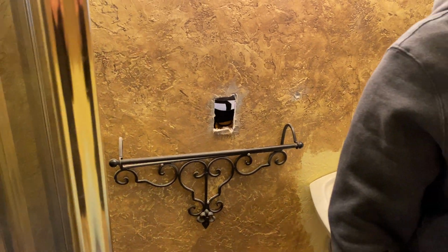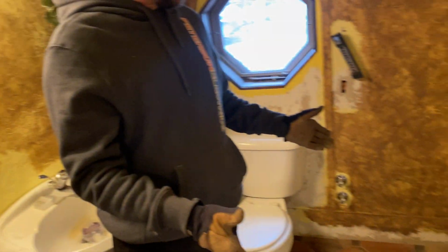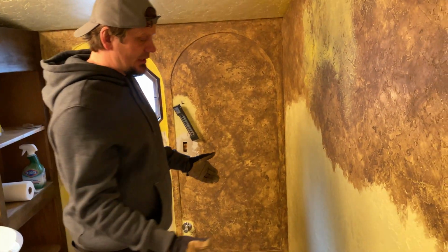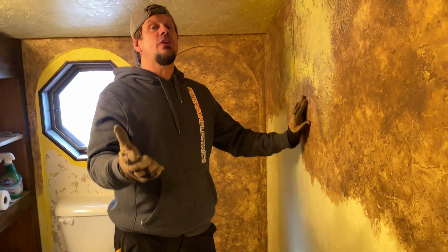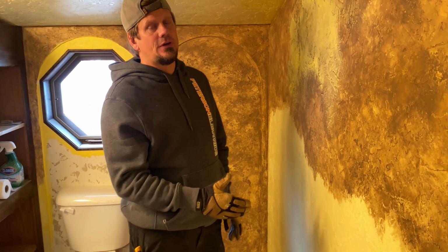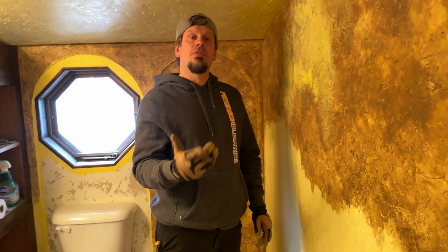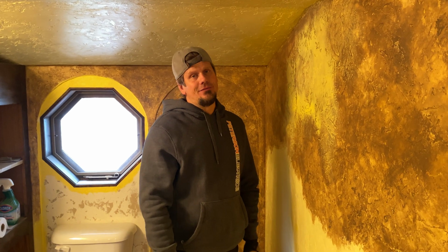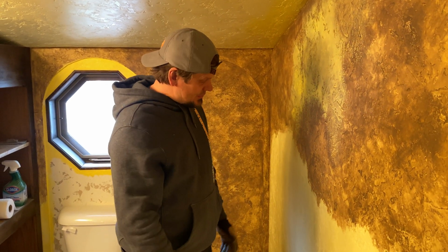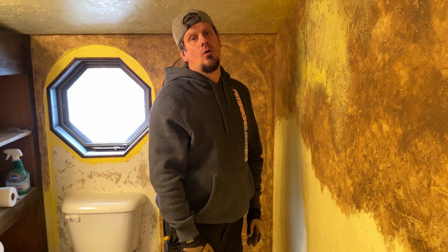Now they also want to get me on that there's not heat in the bathroom. And so there is no 240 volt baseboard heat. And I did argue this with Safe Built if you watch my videos, and I am correct on this. You do not have to GFI protect a baseboard heater that is hardwired in a bathroom. I think it's wise, but you don't have to. But we do have a circuit downstairs waiting.